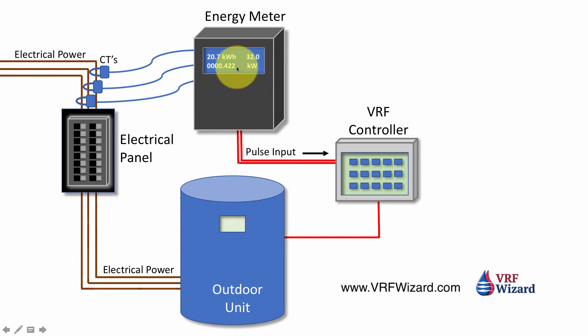That meter collects the data and sends pulse inputs to your VRF controller — in this case a Daikin VRV controller with their PPD software. The PPD software does a calculation for each indoor unit based on its electronic valve position, return air temperature, and factory settings. It determines how much of the energy used at the outdoor unit should be charged to each tenant.